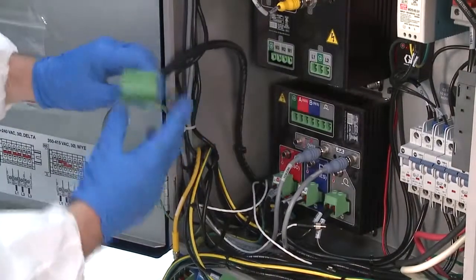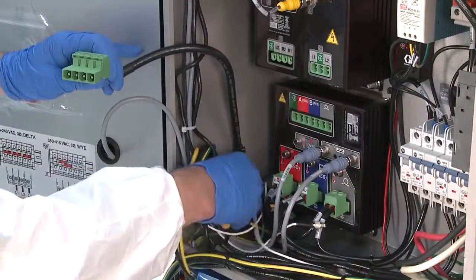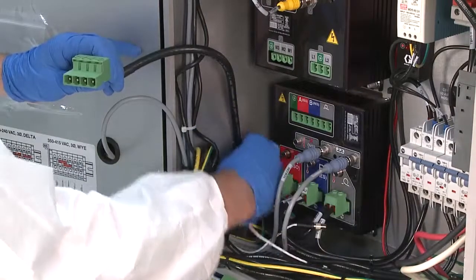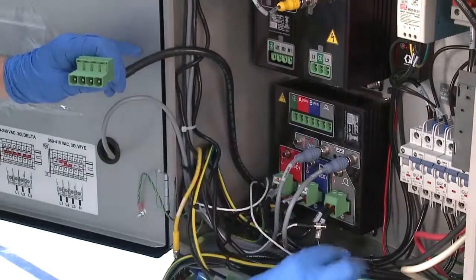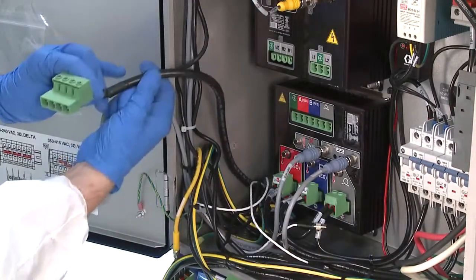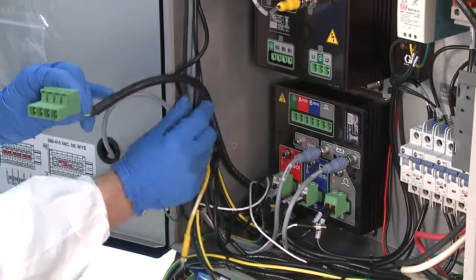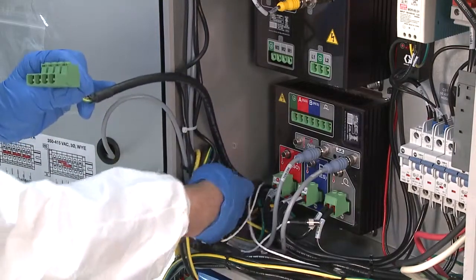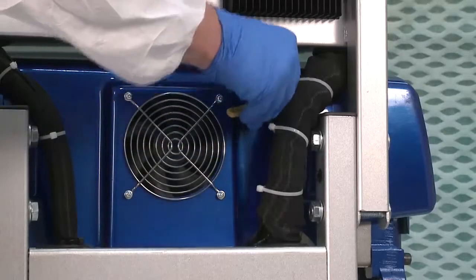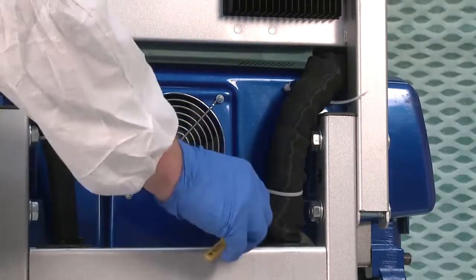Verify insulation and wire are not cut or frayed. Take the time to carefully check both inside the electrical enclosure and behind the system. Think through where wire could be pinched, scraped, or nicked. Inspect carefully in hidden and hard to reach areas with a flashlight.